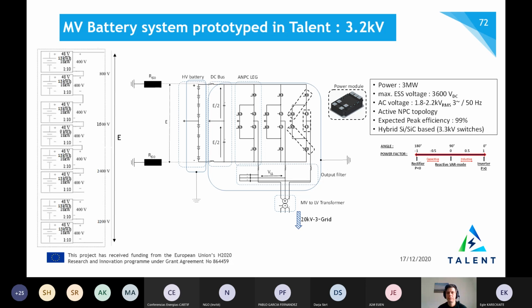The power of the power electronic building block is around 3 megawatts. We can have an input voltage up to 3.6 kV, and the AC voltage can be between 1.8 kV and 2.2 kV. The grid frequency can be 50 or 60 Hertz, that doesn't matter. The topology is an active NPC, and the peak efficiency targeted is 99%. This topology is based on a hybridization of silicon semiconductors and silicon carbide semiconductors in 3.3 kV blocking voltage.